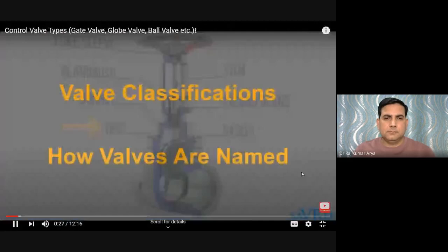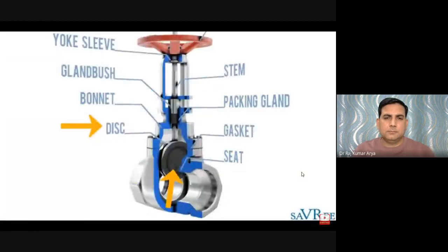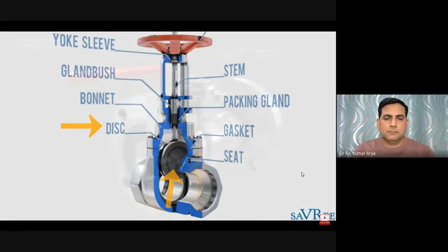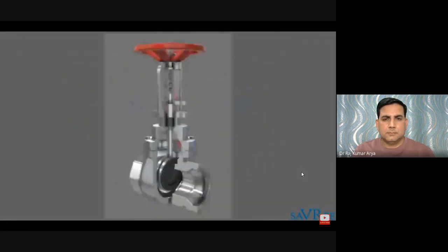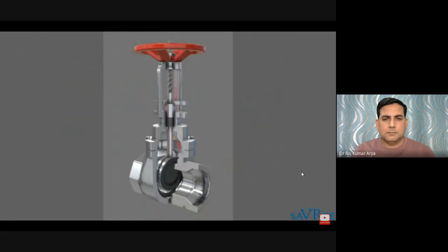Almost always, valves get their name from the type of disc used. A disc is the part of the valve used to open, close, or regulate flow through the valve — regulating flow is referred to as throttling. For example, a ball valve is named because of the ball-like shape of the disc. A butterfly valve is named because of its similar appearance to a butterfly. A gate valve is named because of its similar appearance to a gate. However, globe valves are an exception — they are named after the shape of the valve body itself.